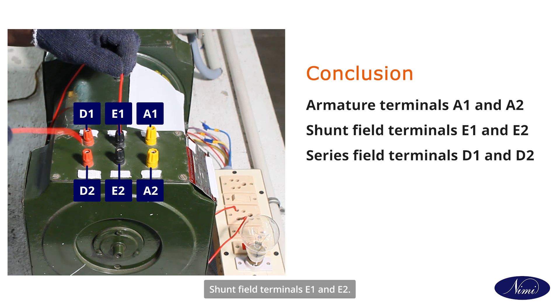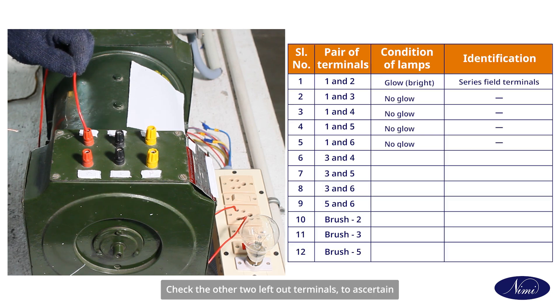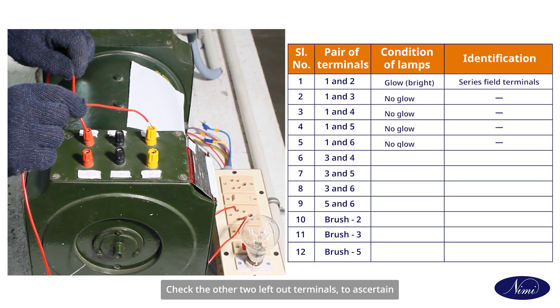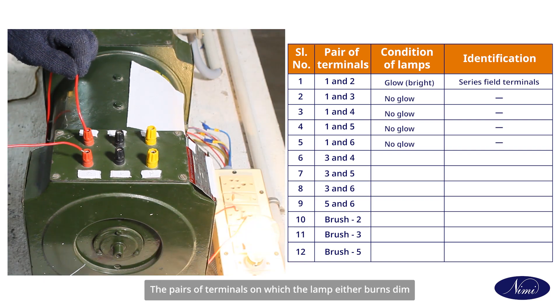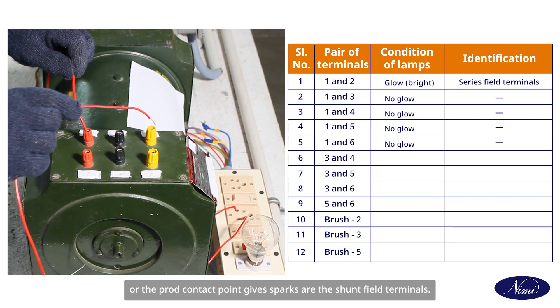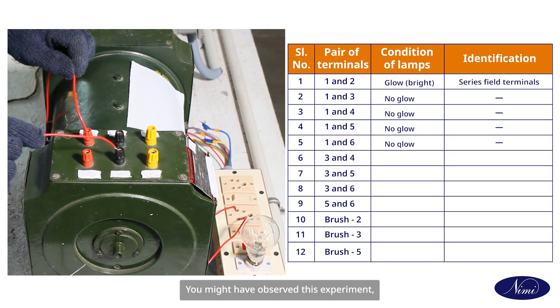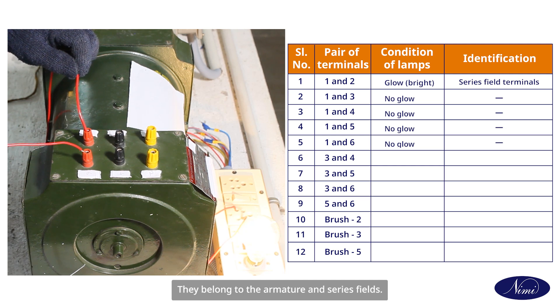Conclusion: armature terminals A1 and A2, shunt field terminals E1 and E2, series field terminals D1 and D2. Check the other two remaining terminals to ascertain whether they belong to the same pairs. The pairs of terminals on which the lamp burns dim or the prod contact point gives a spark are the shunt field terminals. The lamp glows brightly for the two sets of terminals belonging to the armature and series field.